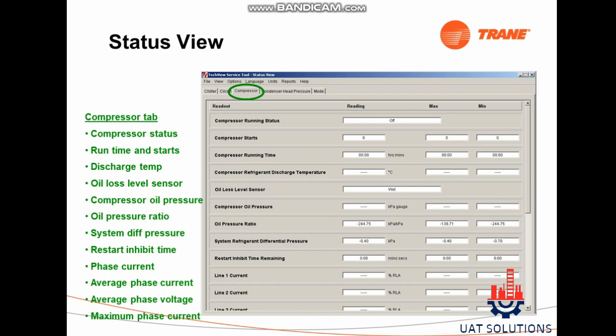Click on the View tab, then click on Status, then click on the Compressor tab to see the following data: compressor status, run time and starts, discharge temperature, oil loss level sensor, compressor oil pressure, oil pressure ratio, system differential pressure, restart inhibit time, phase current, average phase current, average phase voltage, and maximum phase current.